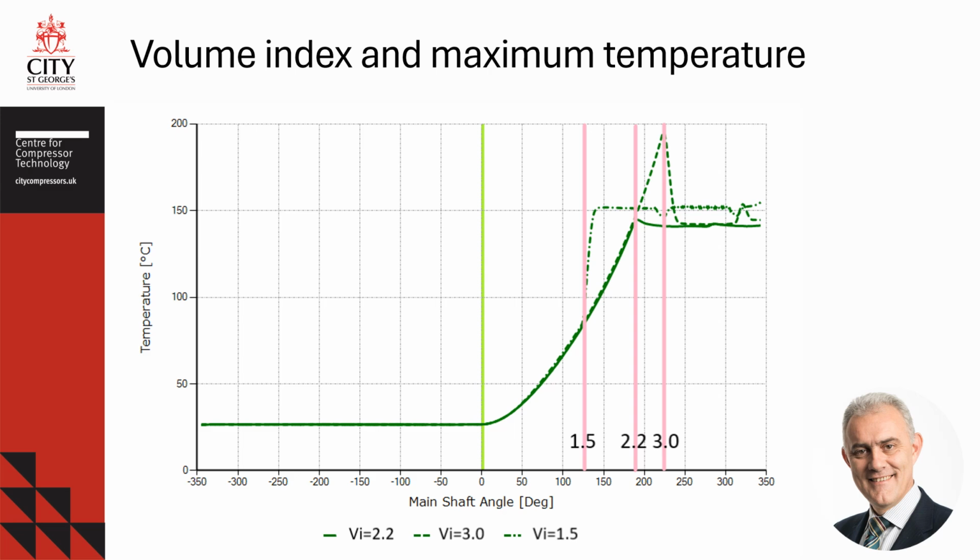Moreover, mismatch in a volume index causes more significant reliability issues for oil-free screw compressors. They are sensitive to the temperature change during compression. Thermal expansion of compressor elements due to the local temperature rise can lead to a contact and compressor catastrophic failure.